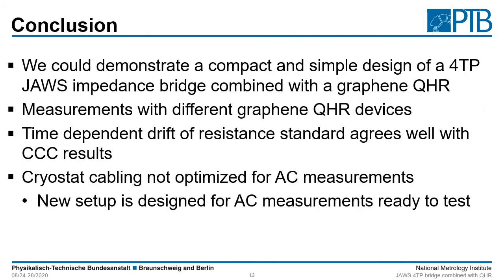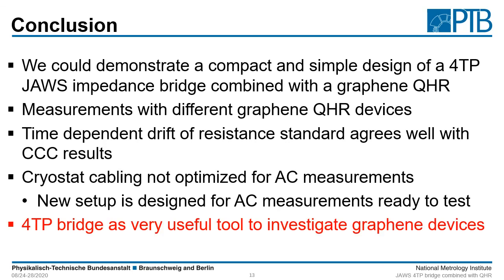Let me summarize. I hope I have demonstrated a compact and simple design of a four terminal pair JAWS bridge combined with an AC quantum hall device. I showed you measurements made with two different graphene samples, and that we can reproduce the time-dependent drift of our resistance standard quite well in comparison to the CCC result. Unfortunately the cryostat cabling was not optimized for AC measurements this time, but we have a new setup designed for AC measurements which is ready to test. Nevertheless, the four terminal pair bridge was a very useful tool to investigate the new graphene devices.